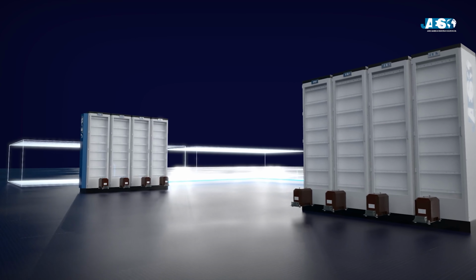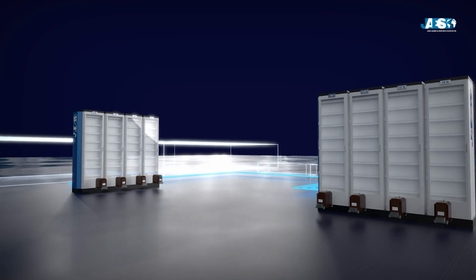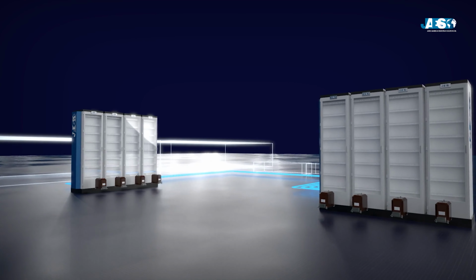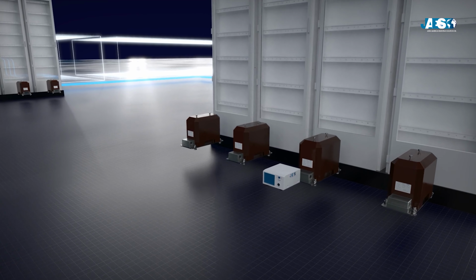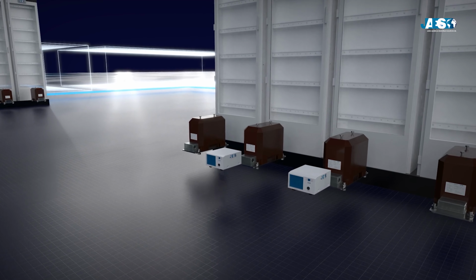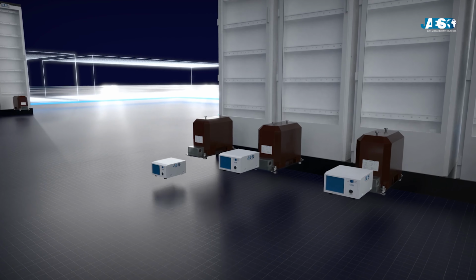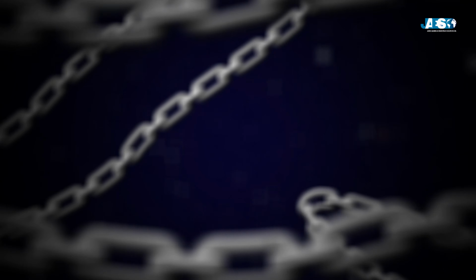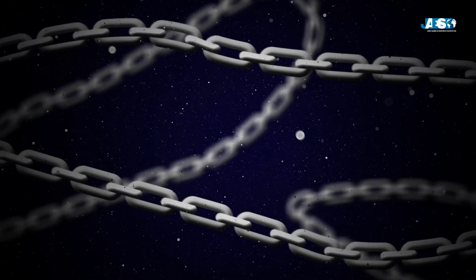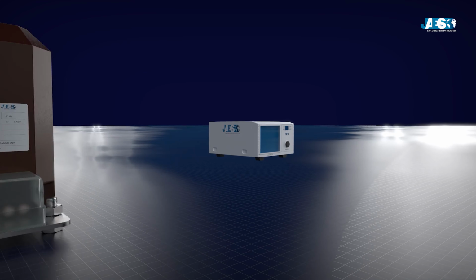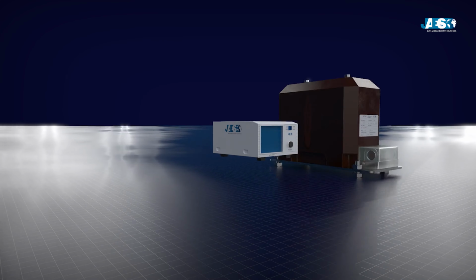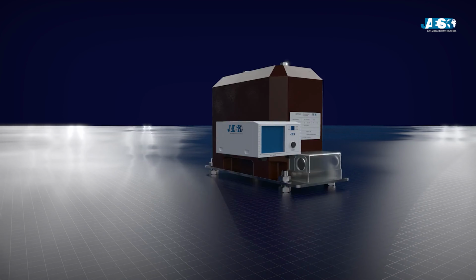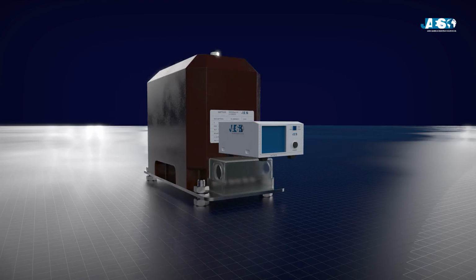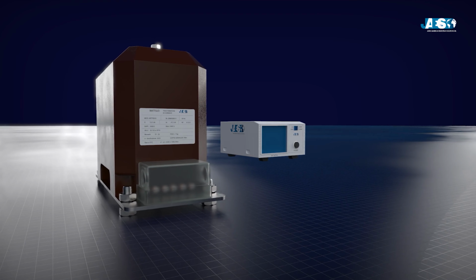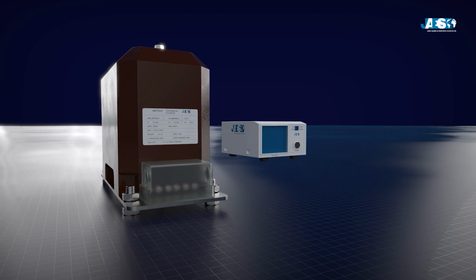The current transformer is a simple component of the system, but plays a very important role because the accuracy of the measurement depends on it. Indeed, it must be taken into account that the CT's own uncertainty must be added to that of the instrument to determine the total accuracy of the measurement. As the saying goes, the strength of a chain is limited to its weakest link. Therefore, it becomes clear that in order to achieve the desired accuracies, it is not enough to choose quality instruments alone, but also equally essential to combine it with a current transformer with a suitable accuracy class and sufficient power.